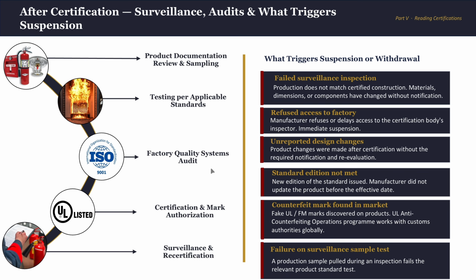And this exists to verify that the factory operates under a quality management system. And this should answer one question: can this factory keep producing what was tested the exact same way multiple times? And after everything is approved, the certification and the mark authorization. If everything passes, the certification mark is issued. The listing is published in the public directory, we'll get to that later, and the manufacturer is authorized to apply the mark to the product.